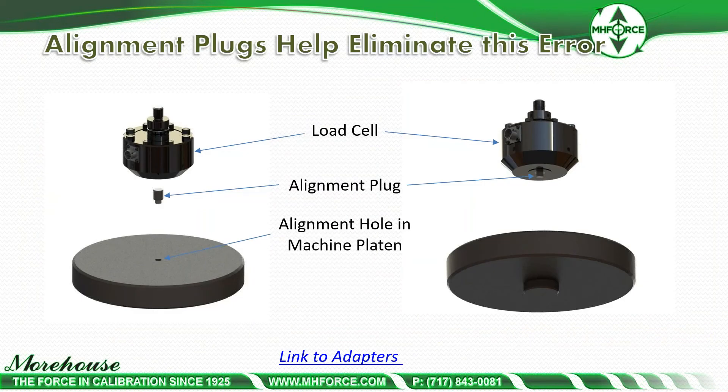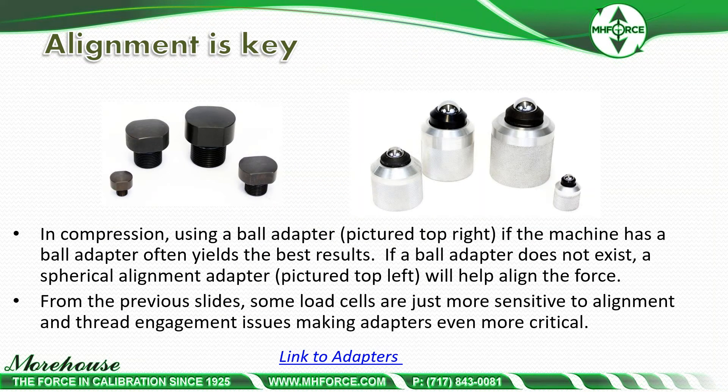Some things we can do to help alignment: the alignment plugs that we manufacture can help. Basically, you have your load cell and an alignment plug, and you have some kind of alignment hole in a machine platen. This can be used in a cal machine, a dead weight machine, or all other types of machines. This alignment plug can be used in the S-beam, the shear web, and all types of other load cells. We also have spherical adapters — for an S-beam, these are probably going to be the recommended adapter of choice. Using a ball adapter, as pictured top right, if the machine has a ball adapter, that often yields the best results. Some load cells are more sensitive to alignment, which makes these adapters all the more critical, and having these with the spherical seat is going to be much better with alignment rings.